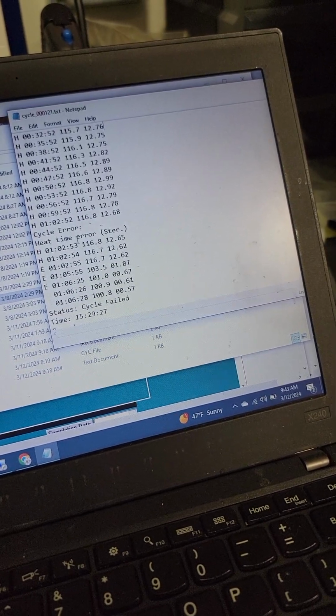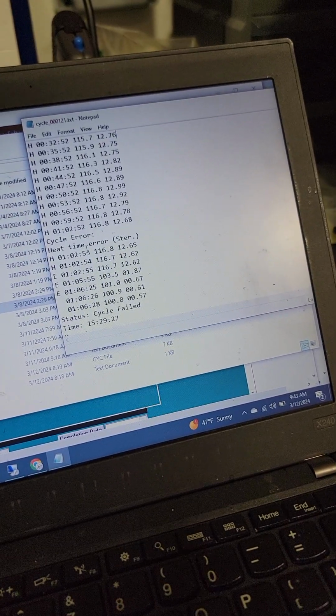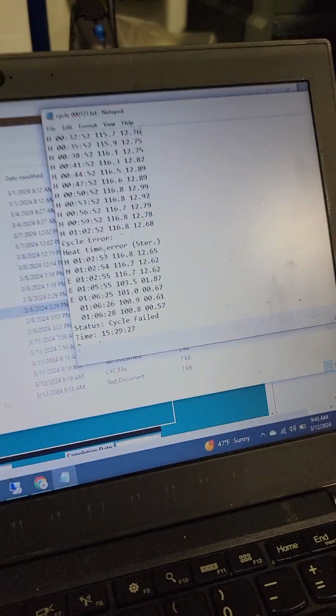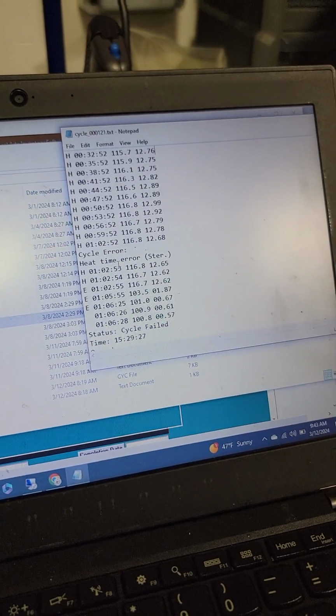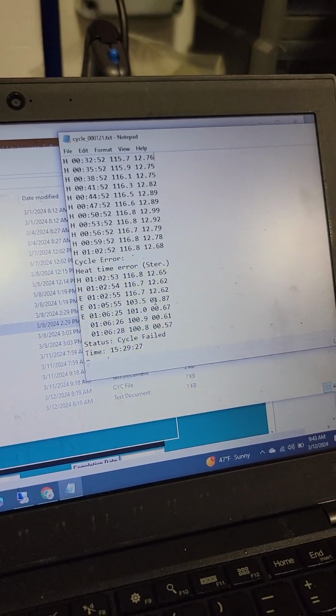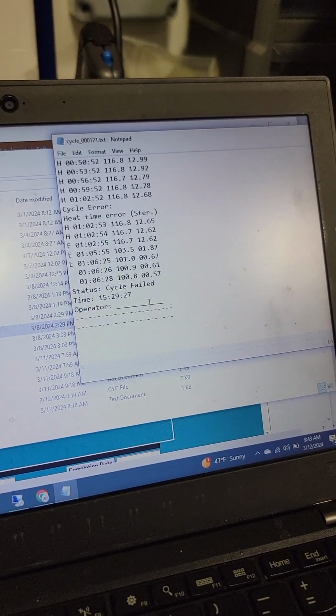So heat up, heat time error means we ran into an error -- we tried to heat up and exceeded the allowable time for the heat up cycle. Can't run forever, so it failed.